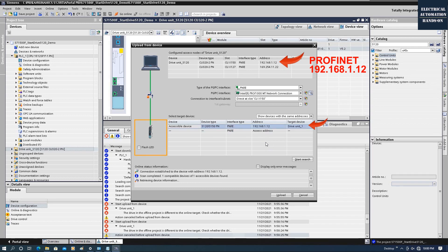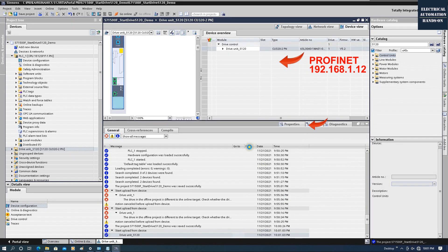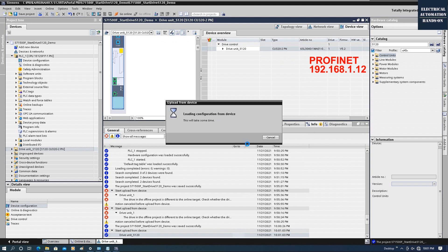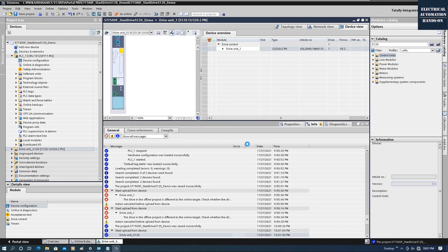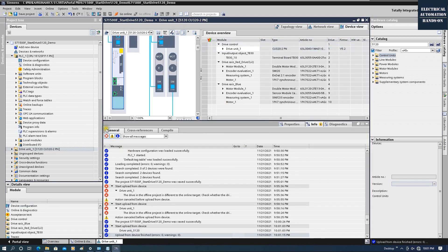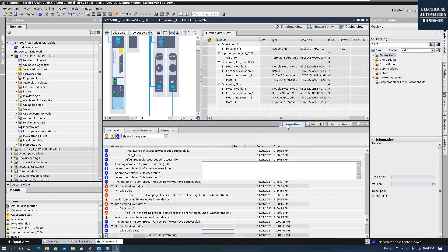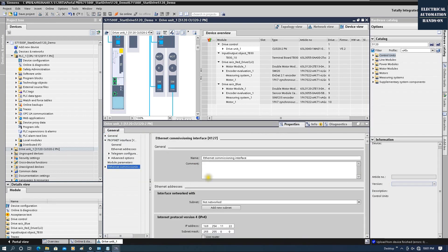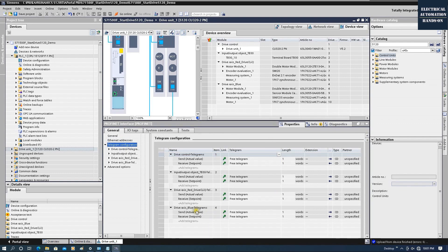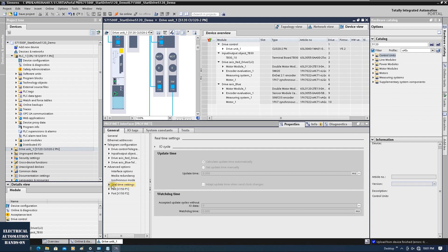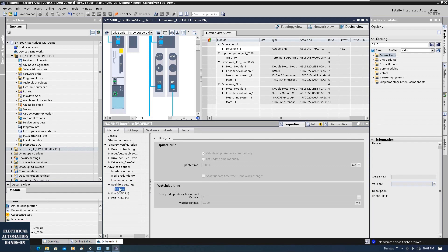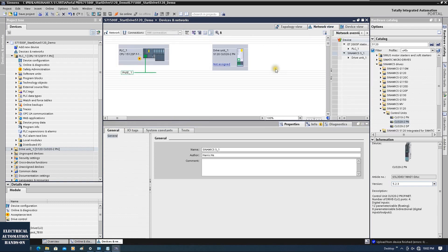Go to the offline configuration, click Search, and the drive is found. Click Online, then Upload — Upload from Device. The software uploads all the hardware configuration including the telegrams; there is a free telegram. I will temporarily use all the default settings here, because in this video our main aim is to set up the PROFINET communication. We will assign the PROFINET device name to set up the PROFINET connection.